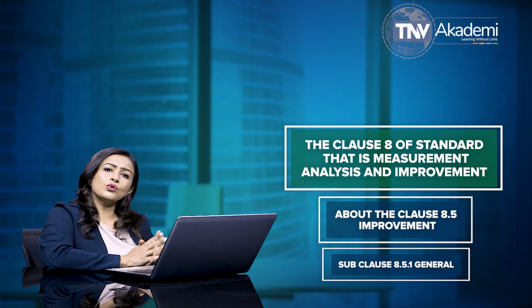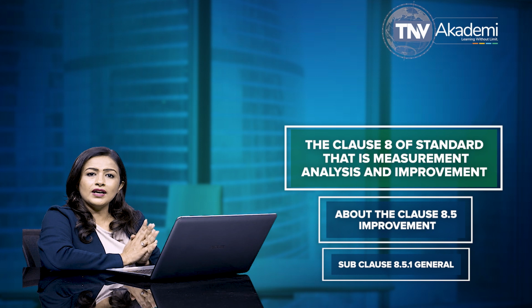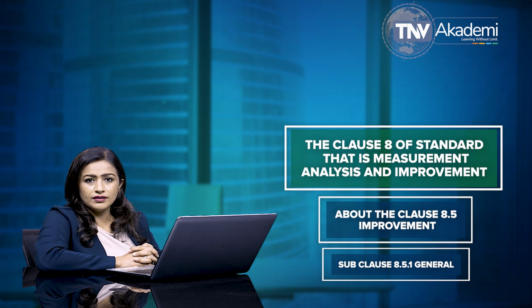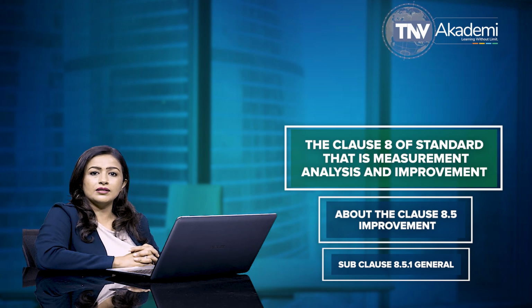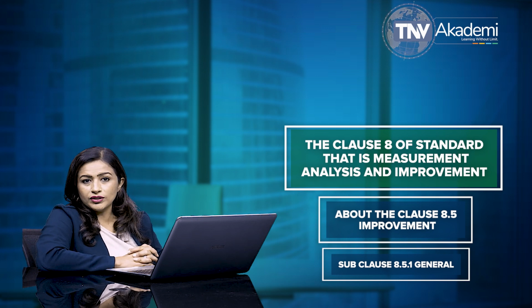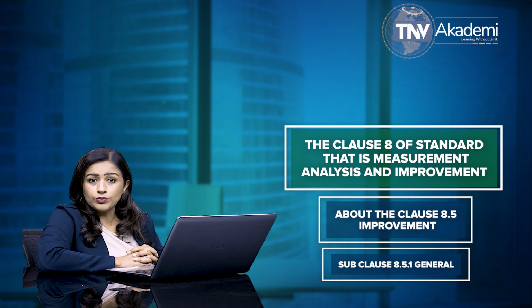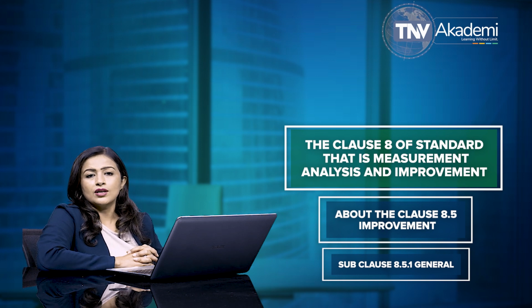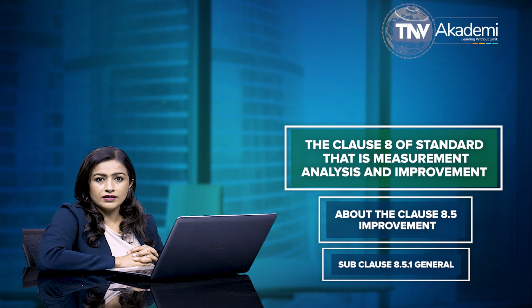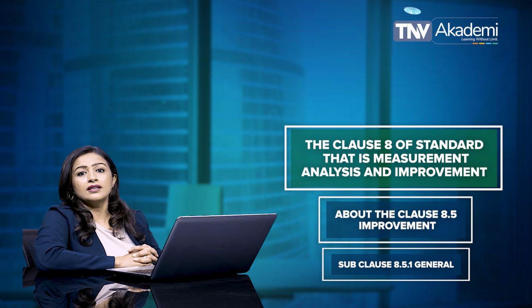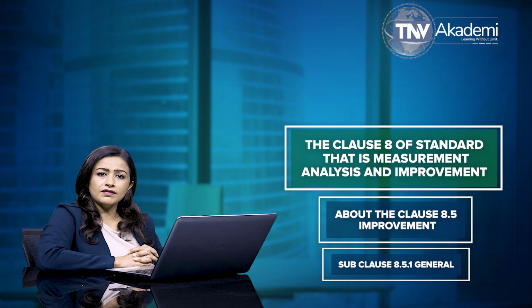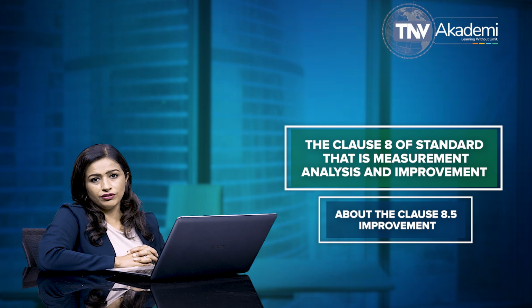The organization is also required to identify and implement any changes necessary to ensure and maintain medical device safety and performance through the use of the quality policy, quality objectives, audit results, post-market surveillance, analysis of data, corrective actions, preventive actions, and management review.